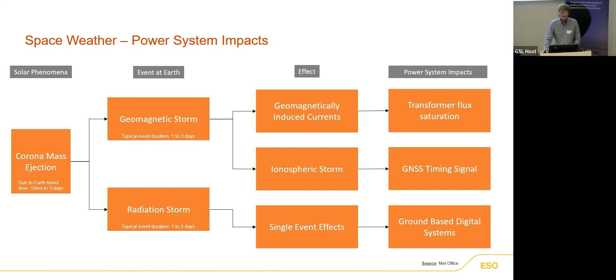Moving on to focus on geomagnetically induced currents: from these currents you can have secondary effects produced by the fact that the transformers are saturated—the magnetic flux within the transformer can be saturated. That can cause transformers to heat up, certain parts getting hot, and in severe cases cause damage and possibly destruction of the transformer. We can also have increased absorption of reactive power, which effectively results in a voltage drop on the transmission system, and we can have harmonics in the current and voltages on the network—essentially noise within the power system.